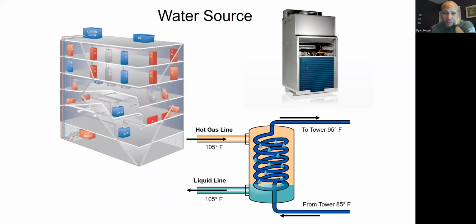I mentioned the water source heat pump earlier, right? So each individual tenant area or zone gets a water source heat pump, which is basically like a little baby water to air chiller. It's taking water off of a water loop from a cooling tower historically. It's getting 85 degree water from a cooling tower, dumping heat from that zone into the water, and sending 95 degree water back out to the cooling tower to be cooled. So there's a refrigerant to water heat exchanger in here. Each of these machines has this heat exchanger, and they have a compressor in there. And then on the air side, they have a refrigerant to air heat exchanger.